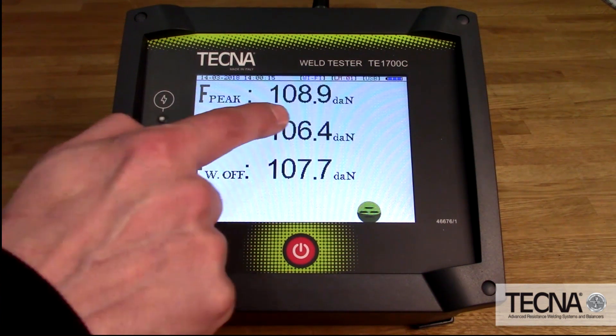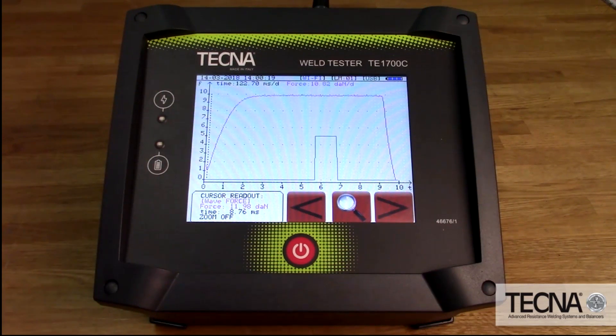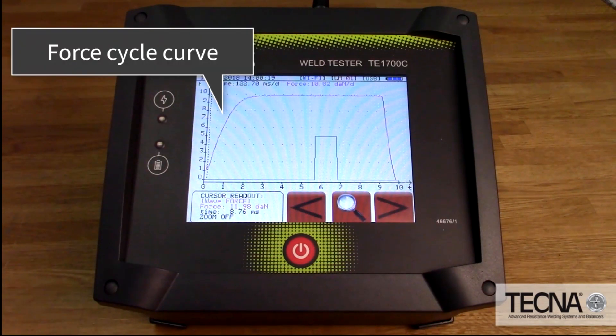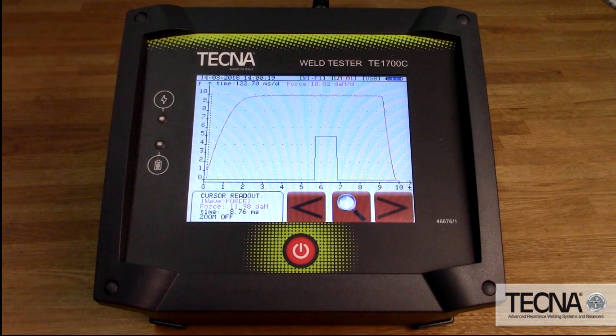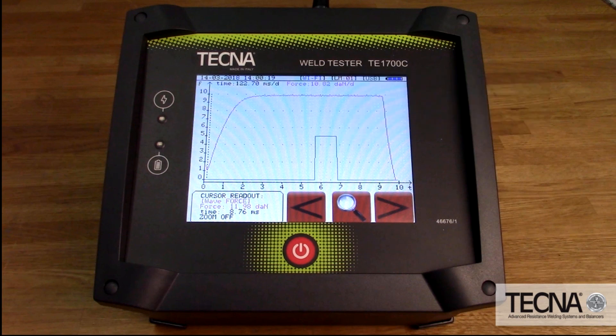A graphical display showing the force cycle curve can be displayed. Even though you can't pass current through the sensor, it can detect when voltage is applied and provide a graphical representation of when weld time starts and ends. The direction buttons can be used to check the force value at specific points during the weld. You can also use the zoom feature to take a closer look at specific points within the waveform.